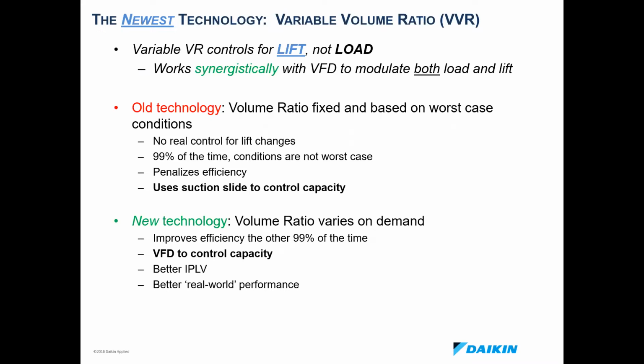And now the new way that it's done is we have a slide valve on the discharge side of the screw, which will allow the compressor to vary for lift. It'll be able to modulate for lift conditions, and then the VFD will be modulating the mass flow rate of refrigerant through the compressor, which will be modulating for your capacity.